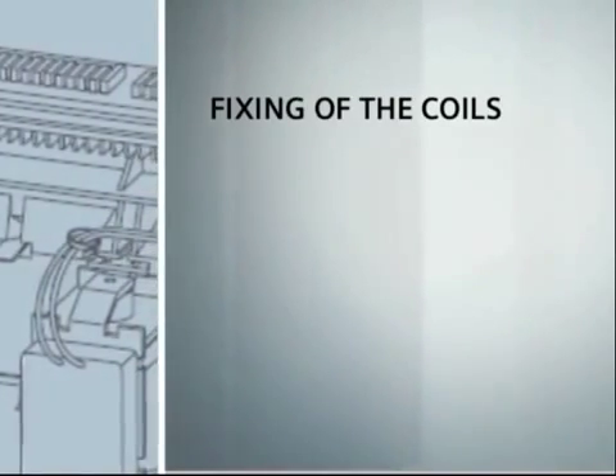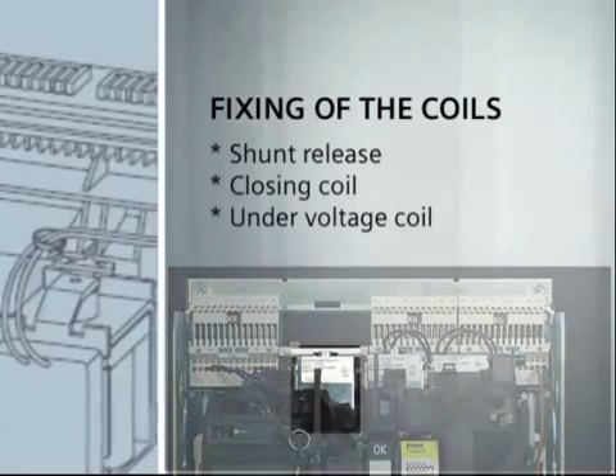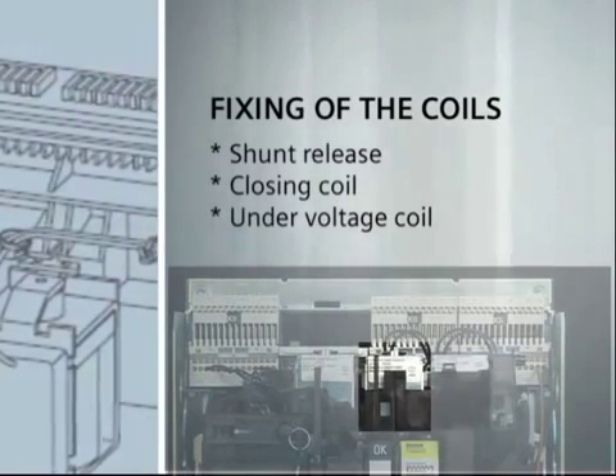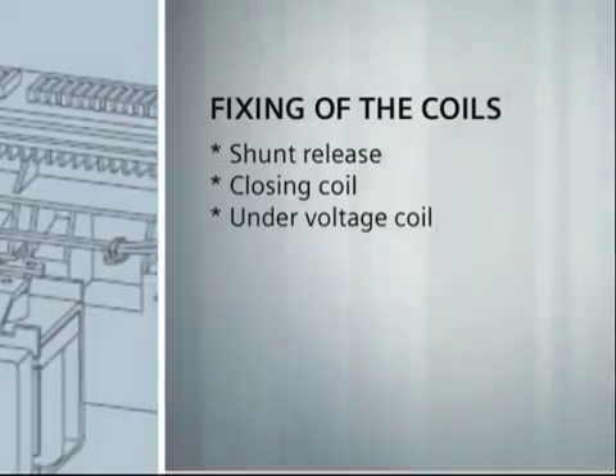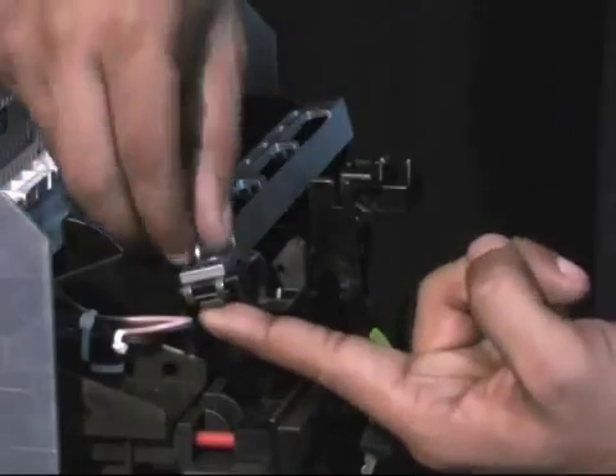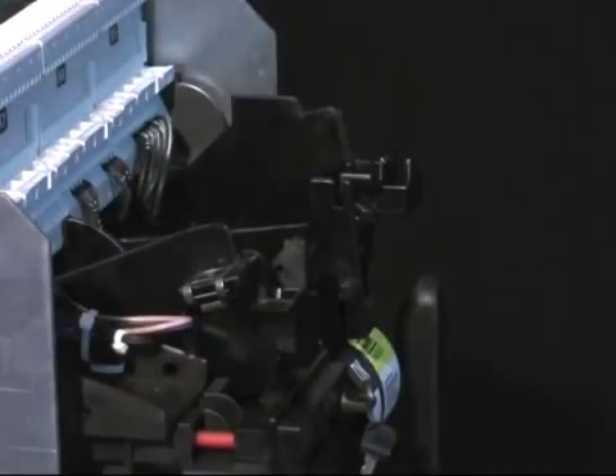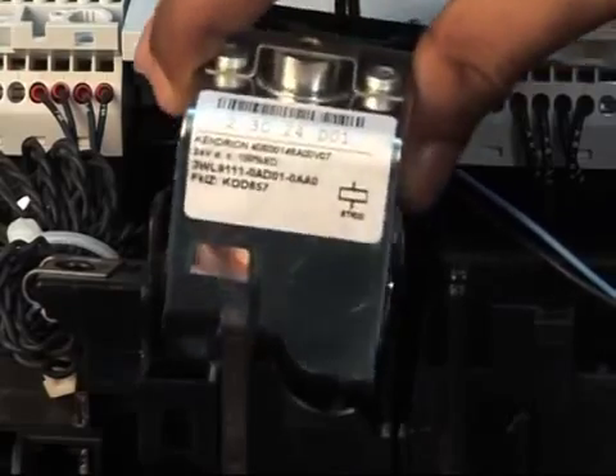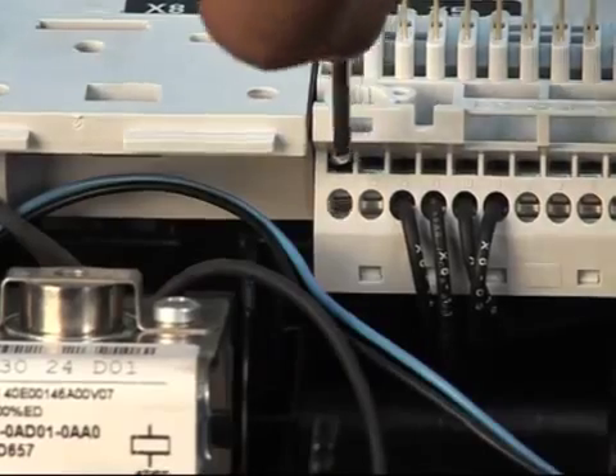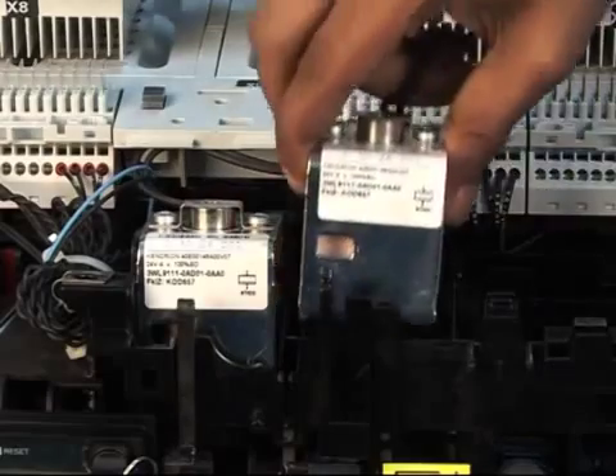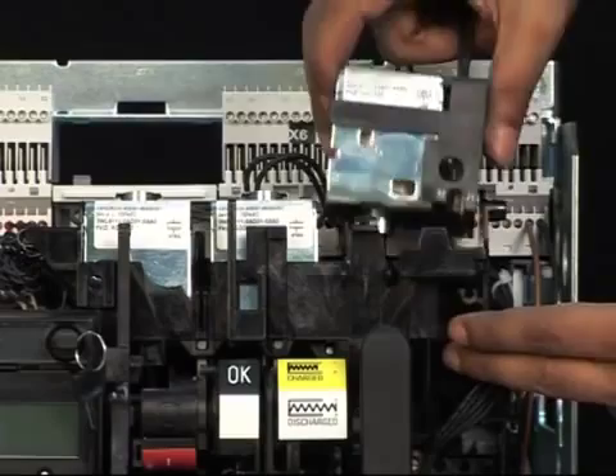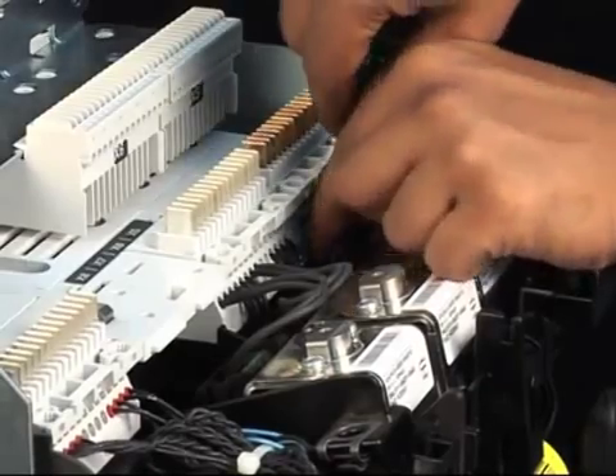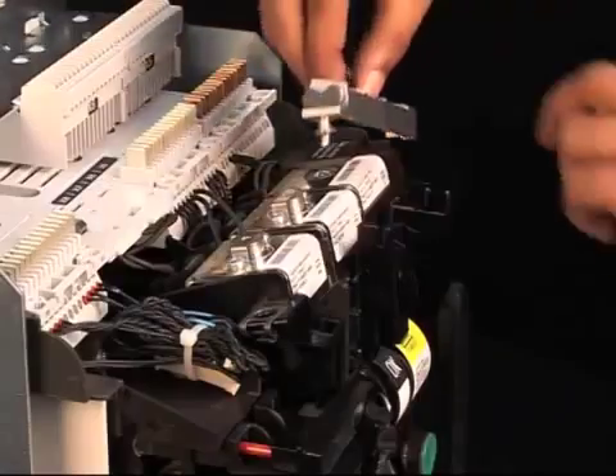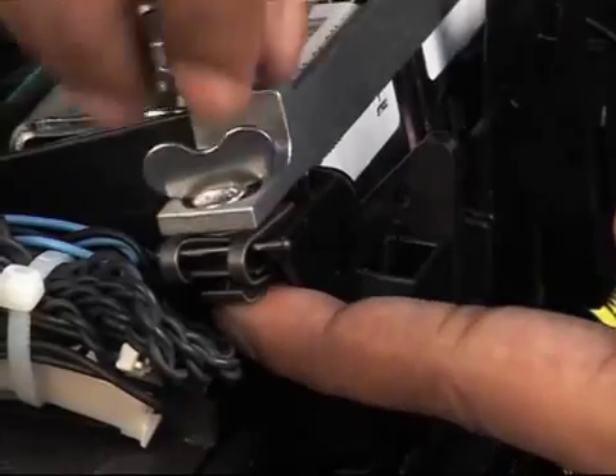Now we shall demonstrate fixing of the three coils, namely shunt release, closing coil and under voltage coil, one by one. First, please remove the retainer bracket which holds the three coils in place. Before the attempt to install the coils for a withdrawable breaker, it's drawn out. The coils are put one by one and the connections are made through the auxiliary terminals. Connection becomes simple and quick thanks to the innovative screwless cable terminals. The retainer bracket is fixed again and the operator panel is put back.